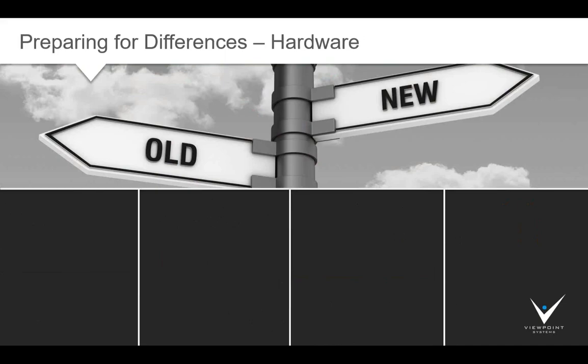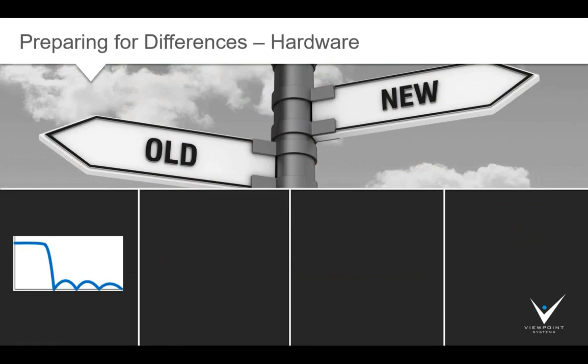I'll describe some examples of actual upgrade projects we did. In the first example, we had a customer with a very old manual tester where the operator was writing down readings on panel meters, looking at the values and writing them down on a pad of paper. These panel meters had analog low-pass filters built in to stabilize the visual display. But the new system, using high-speed analog digitizers, was much more responsive.